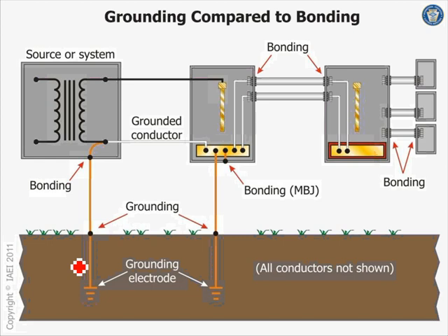So this is pipe, and I'm bonding this pipe to this enclosure, even though I'm putting an equipment ground conductor inside it. Even if I put an equipment ground conductor here, I still have to bond the enclosure to the pipe. That's where bonding becomes slightly different than grounding. Any comments, any questions, guys? Corrections?